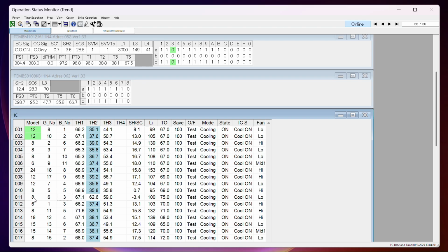In fact, I know that every one of these is good because I did the startup on this system a year or so ago. Oh, and if you noticed, I've been highlighting the model numbers. I do this to keep track of which units I've successfully verified the port assignments for. I will just keep doing that, and then I'll typically highlight here and start recording a log of what's wrong and what it needs to change to afterwards.